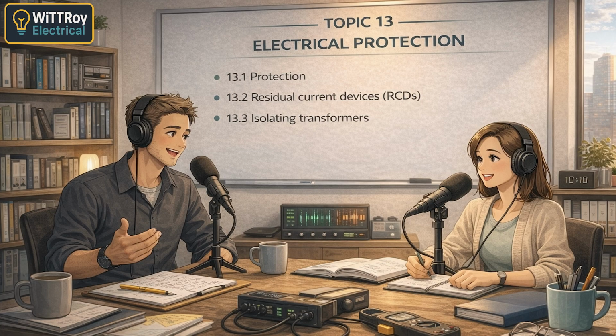Okay. Now, installation requirements. Where are RCDs required? So on most final subcircuits in residential installations. Correct. Can you name some? Socket outlets. Yes. Lighting circuits. Correct. Fixed wired appliances. Yes. And what about locations? Damp locations. Such as? Bathrooms, laundries, outdoor areas. Correct. Why are these higher risk? Because people are wet and body resistance is lower. Exactly. So RCD protection is essential there.